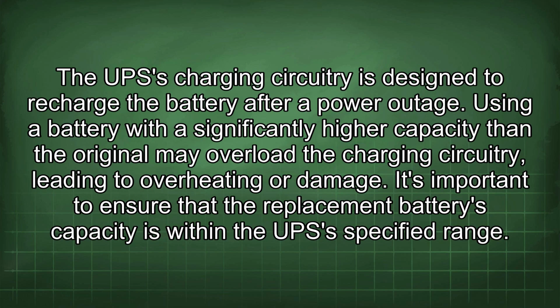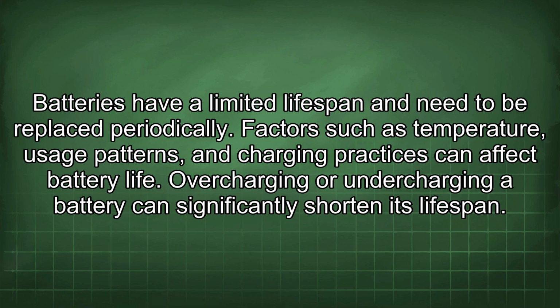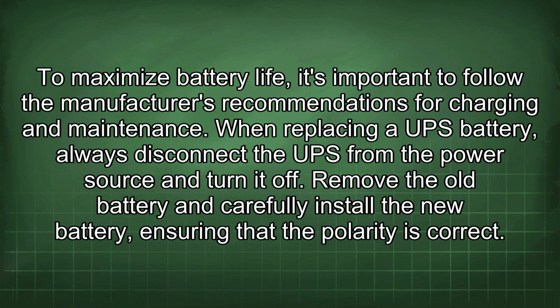runtime. The UPS charging circuitry is designed to recharge the battery after a power outage. Using a battery with a significantly higher capacity than the original may overload the charging circuitry, leading to overheating or damage. It's important to ensure that the replacement battery's capacity is within the UPS specified range. Batteries have a limited lifespan and need to be replaced periodically. Factors such as temperature, usage patterns, and charging practices can affect battery life. Overcharging or undercharging a battery can significantly shorten its lifespan. To maximize battery life, it's important to follow the manufacturer's recommendations for charging and maintenance.